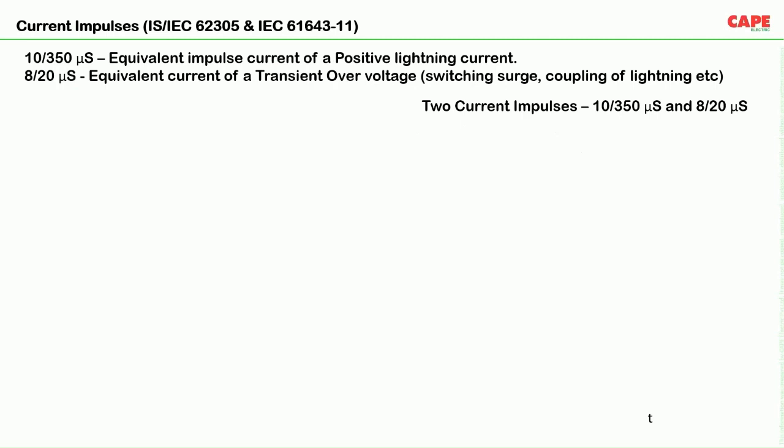Generally, lightning is going to strike and we don't know how it will behave. For the sake of testing and measurement, standards have defined two types of current impulses. The first is the 10/350 microsecond current impulse, which is the equivalent impulse current of a positive lightning strike. The second is the 8/20 microsecond current impulse, which is equivalent to the current of a transient overvoltage — surges generated due to switching or coupling of lightning.